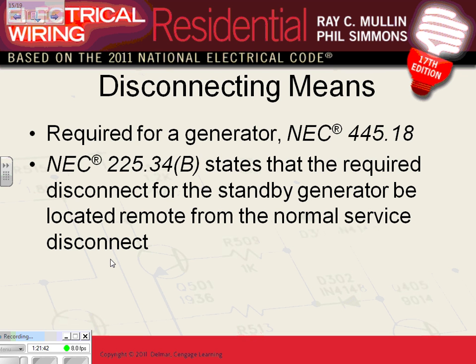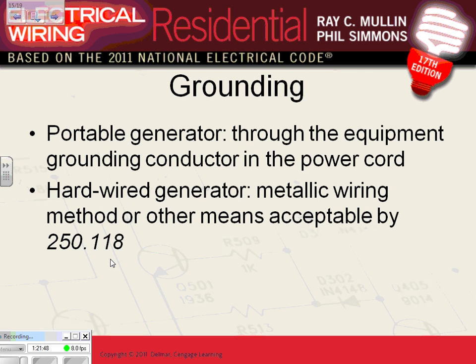Generator to be located: you have to have a disconnect next to the generator, guys. The mounted generator is right next to the generator, within sight of the building, so you can disconnect the power. If it's portable equipment, talked about the portable generators, they allow you to ground them through the plug, which is really interesting. I don't want to open this can of worms, Zach. But the frame of the portable generator is actually bonded and grounded through the equipment grounding conductor that comes in the cord and the plug, which we don't do that often. But this is only for the portable ones, the ones that you haul, up to 15 kW.